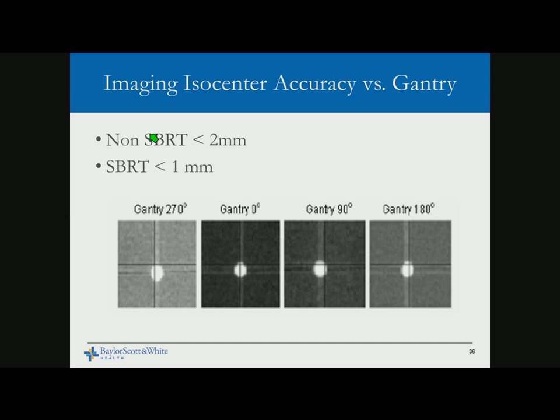Checking the imaging isocenter is especially important from an SBRT perspective. Many places are moving away from using body frames or physical head frames for cranial treatments. The real stereotaxy of treatment now comes from imaging — how we assure sub-millimeter accuracy is because of imaging, which makes the treatment stereotactic. We need sub-millimeter imaging accuracy since we are no longer relying on body or head frames for lung SBRT.